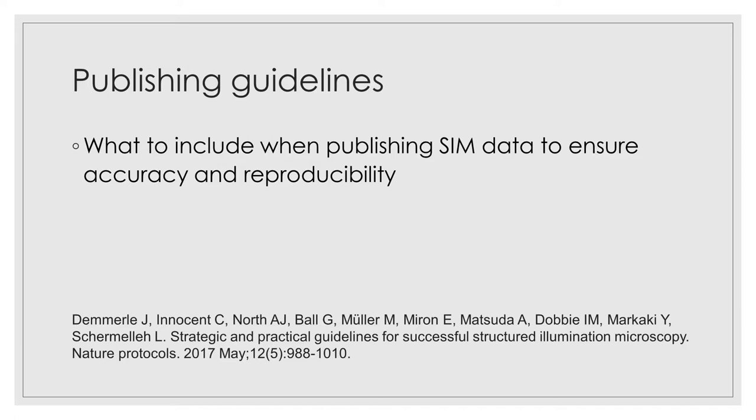The full details are in this paper, but here are some key points. It's important to include the raw and reconstructed data, the full 16-bit or 32-bit images in a database. Also, it's important to include the calibration OTF files for repeatability. Don't discard negative values in the reconstruction process. Some commercial software may do this automatically. If more than one fluorescence channel is used, explain how the channels were aligned. Check that what you think is a biological structure isn't just a reconstruction artefact. If it's a repeating pattern of structured shapes, it's probably an artefact. Add any other filter settings, such as the Wiener filter, which is used to filter noise, and explain how the OTF was obtained and how it matched the sample PSF. You can also experimentally measure the resolution, such as by measuring the full width half maximum of diffraction-limited beads, and use this rather than the theoretical resolution. And it's also important to add the system configuration details and the acquisition parameters.